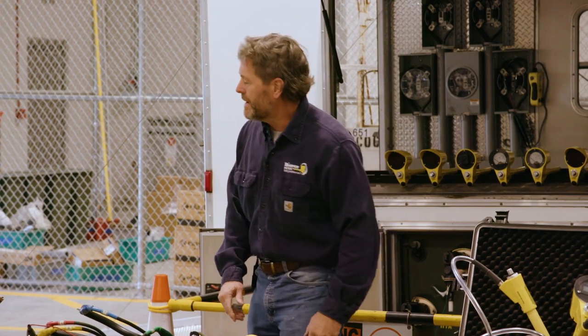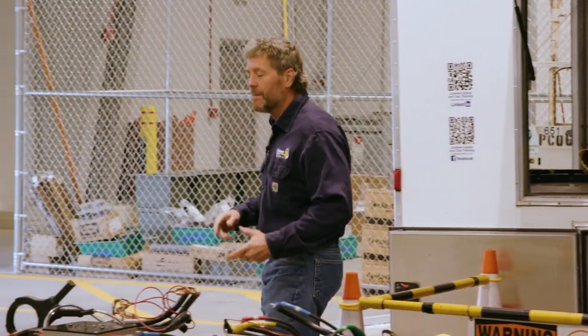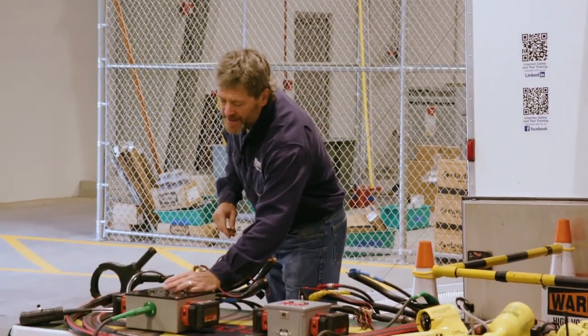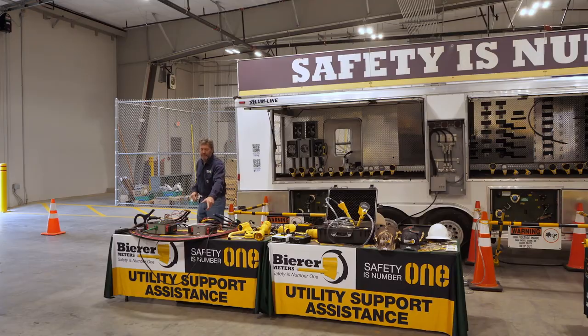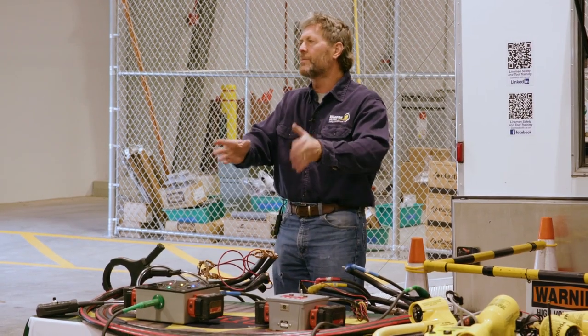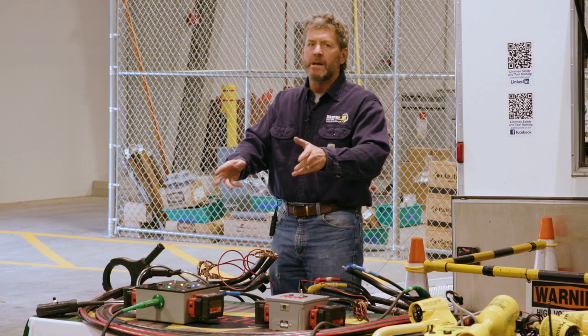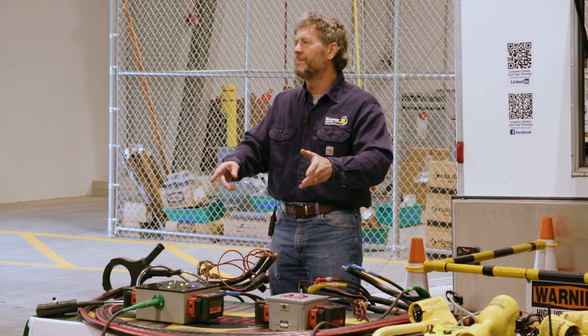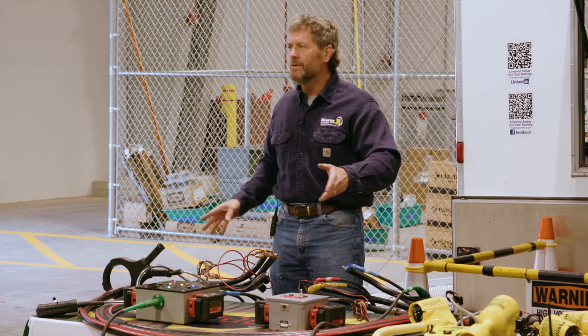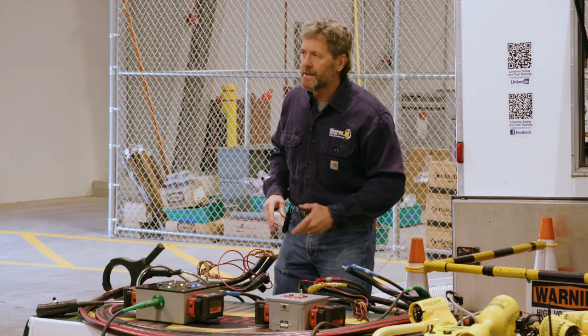Five functions, pretty cool. All right, we're almost done. Real quick, I'll also mention psychological safety in a bit. We've got a three-phase ID and a single-phase ID. I'll skip the single and go straight to the three-phase, because it does what the single does, times three. It gives you A, B, or C on a de-energized primary cable, and it works through about two to three splices. After three, it loses too much of the load, the pulse, and you can't read it anymore. But up to three, it works well.